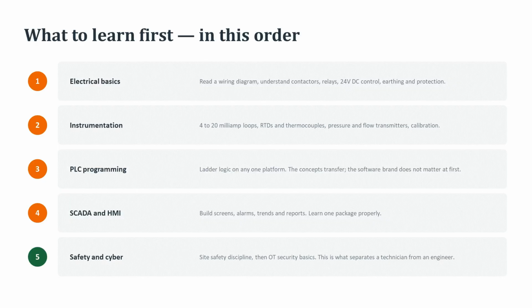If you decide to start, learn things in this order. First, electrical basics, so you can read a wiring diagram and understand contactors, 24-volt control, earthing and protection. Second, instrumentation: the 4 to 20 milliamp loop, thermocouples, and pressure and flow transmitters. Third, PLC programming, ladder logic on any one platform, because the concepts transfer even if the brand changes.